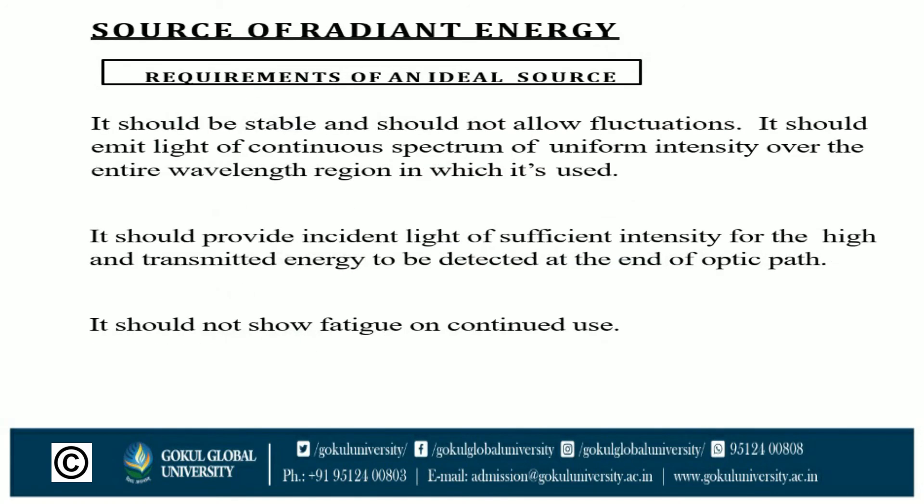Source of radiant energy: requirements of an ideal source — it should be stable and should not allow fluctuations. It should emit light of a continuous spectrum of uniform intensity over the entire wavelength region in which it is used. It should provide incident light of sufficient intensity for the transmitted energy to be detected at the end of the optic path. It should not show fatigue on continued use.